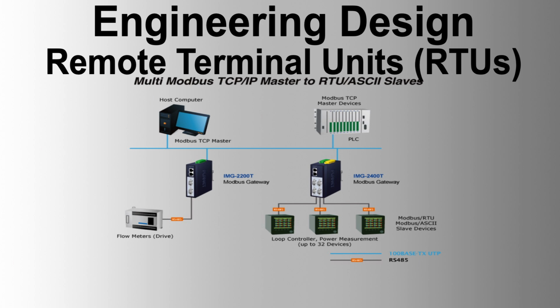Analog input requirements. The analog input (AI) requirements for RTUs are designed to ensure accurate and reliable data acquisition from various sensors and instruments. Below are the key specifications and features. Input wiring. Individually isolated inputs. Hardwired analog inputs should be connected to the RTU through individually isolated inputs rather than input multiplexers. This ensures better isolation and reduces the risk of cross-interference.